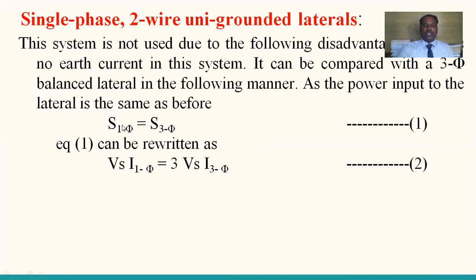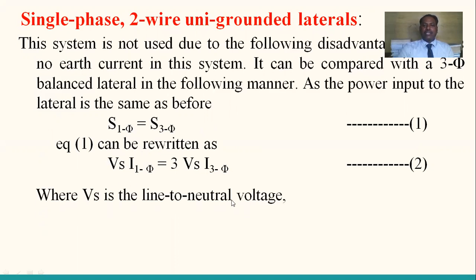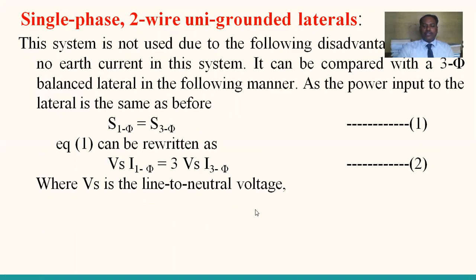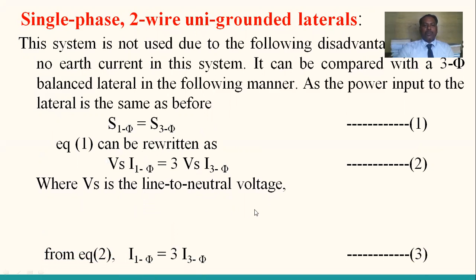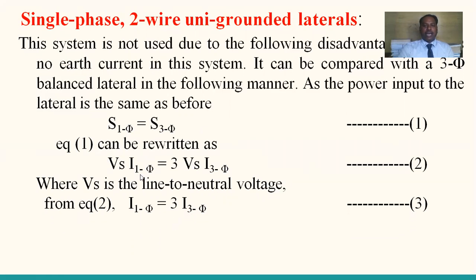In equation number 1, the loads are constant. By comparing the single phase two-wire uni-grounded system with a three-phase balanced system, the load should be constant, in the sense that S single phase is equal to S three phase. From equation 1 you can write equation 2 and simplify it. Here Vs is the line to neutral voltage. Simplifying equation 2, I single phase is equal to 3 times I three phase when the two-wire uni-grounded lateral is used.